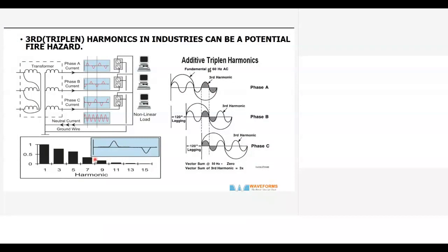Normally the other phases, A, B, C, or R, Y, B, are at a 120 degree phase shift. So at the neutral the vector sum will be 0. But if you take the third harmonic, they add up in the neutral, and so now it can be 3x. Like I told you, in an industrial plant with 100 amps in each phase, there will be 300 amps in the neutral. That is a very dangerous situation.